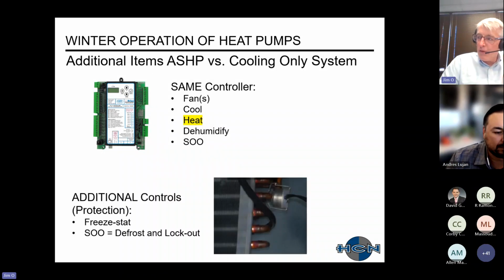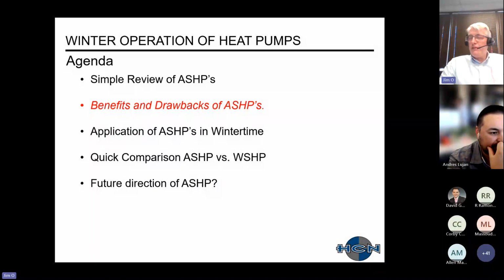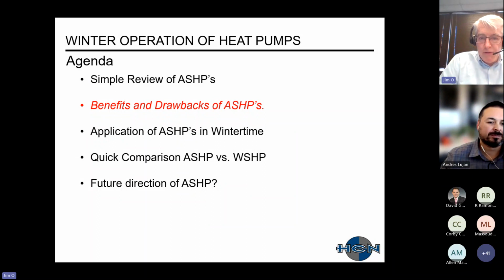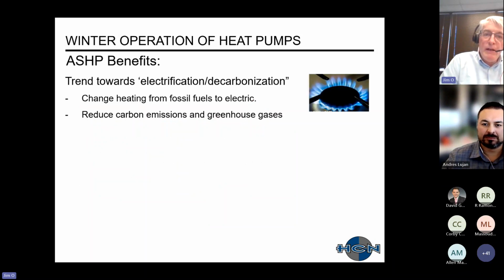And then from a control perspective, the main thing is that we've added a little thermostat, shown on the condenser coil, for protection. So it serves as a freezestat, and it will also help with lockout and also our defrost mode that I will talk about more in depth. All right, the benefits and drawbacks of air source heat pumps I'll talk about next.